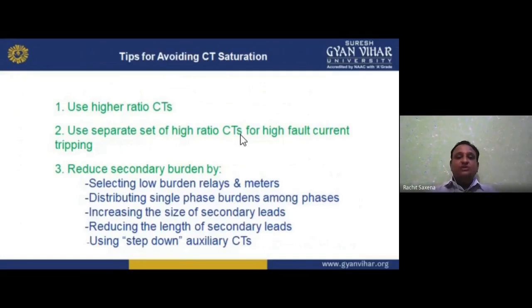Tips for avoiding saturation: use higher ratio CTs, always higher, not low ratio CTs. Use a separate set of high ratio CTs for high fault current tripping. Reduce secondary burden by selecting low burden relays and meters. Distribute single phase burdens evenly among phases. Increase the size of the secondary leads. Reduce the length of the secondary leads. Use step down auxiliary CTs. So we can do it with the help of this.